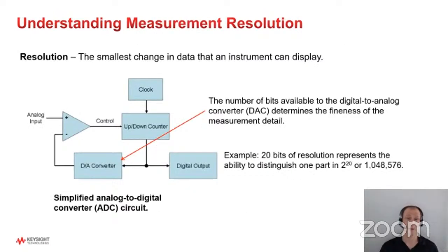In parametric tests, one of the most important parameters is the resolution of the equipment that we're using. Resolution is simply the smallest change in data that an instrument can display. The way I sometimes like to think about this is that we're converting an analog signal to a digital value, a number, and you can consider that in terms of an analog to digital converter. The accuracy of that is determined by the number of bits in the converter, as shown in this simplified circuit diagram. For example, if you have 20 bits of resolution, that represents roughly the ability to distinguish one part in 2 to the 20th power, or about a million. So this is a very important parameter for parametric test.